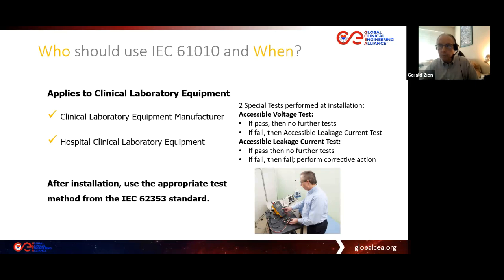So if the accessible voltage test is performed and it passes, no additional tests are required for 61010. This is done by the manufacturer at their location. Sometimes it may be done by an installer, whoever is installing that big clinical laboratory equipment, but the results of this need to be included in the handoff test report that we get before we go live with this equipment in our location.